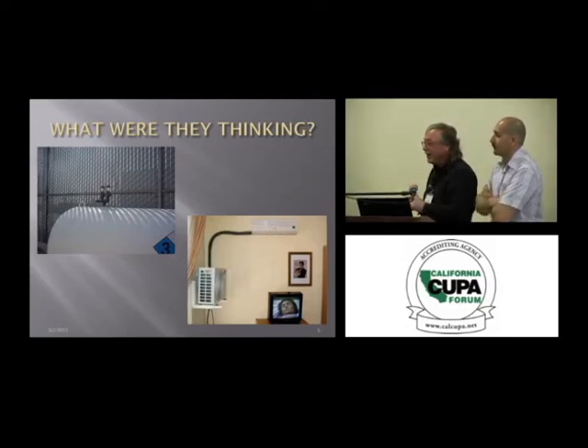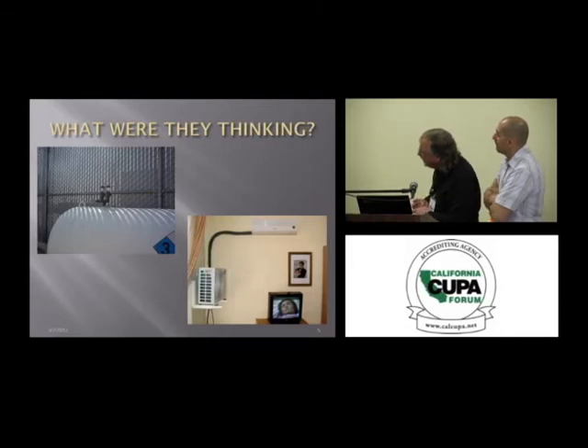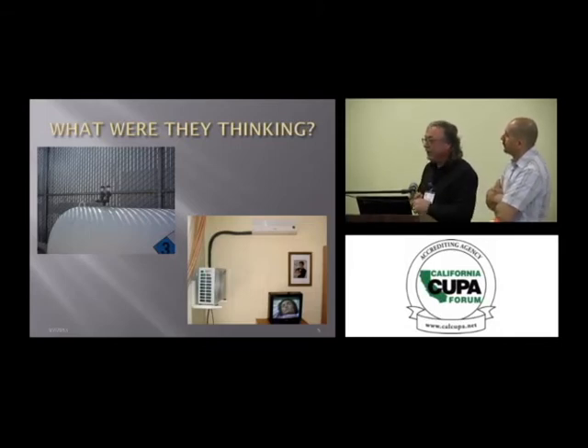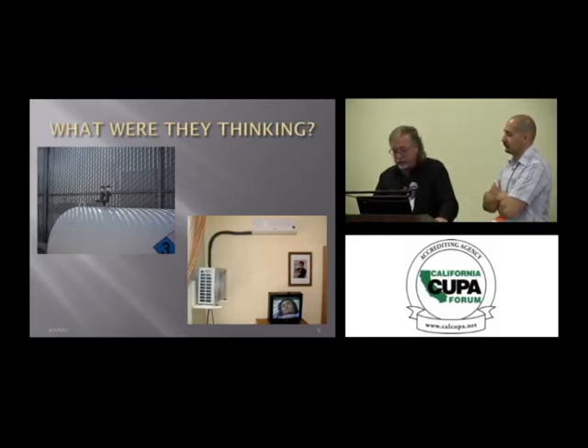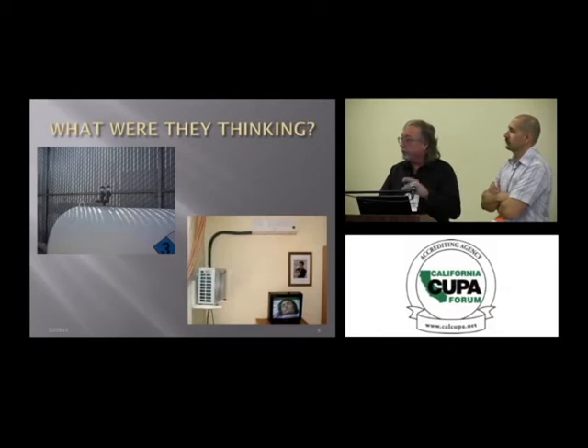Say that again? Nope. On the left-hand side picture, those are pressure relief valves on top of a high-pressure receiver, right at face level. The outlet's right at the operator when they're filling that tank. Okay. Bottom right-hand side, that's just a condenser and evaporator in a room. So you're not doing air conditioning. When you're looking at a refrigeration system, we're talking about the condenser that's typically outside. That's where we get rid of the heat. Okay, that would be here. And then we have the evaporator where we absorb the heat into the system.